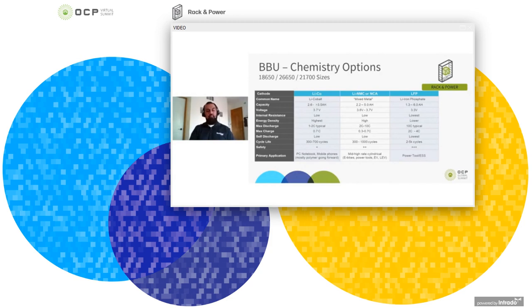Iron phosphate or LFP can also be a good option for BBUs. They offer very high power density, is one of the safest lithium technologies, and they can handle high temperature excursions. But their big drawback is low energy density and higher costs. But with the additional safety and thermal mitigations you have to add to the other chemistries to keep them safe, a total LFP BBU solution is coming very close to the cost of an NMC or NCA solution. And with the recent advancements in LFP technology bringing the cost down, LFP can still be a very viable solution for BBUs.